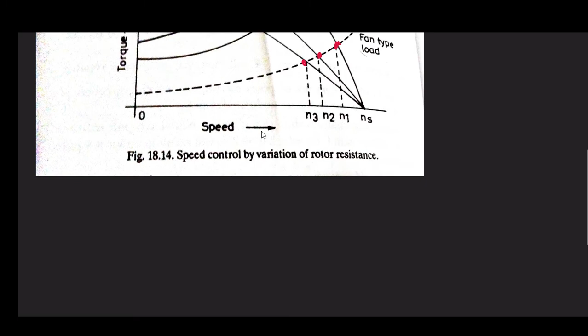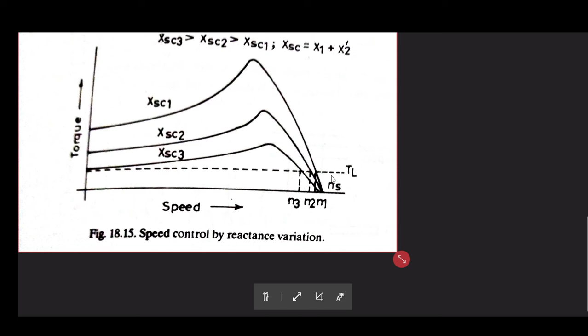Another thing we can do is vary our reactance, and that will directly affect the torque profile of our machine. You can see that with increasing value of reactance, our torque will be severely reduced. It is almost like varying the voltage, but that is also not a good approach. So what we do is what is known as rotor slip power control.